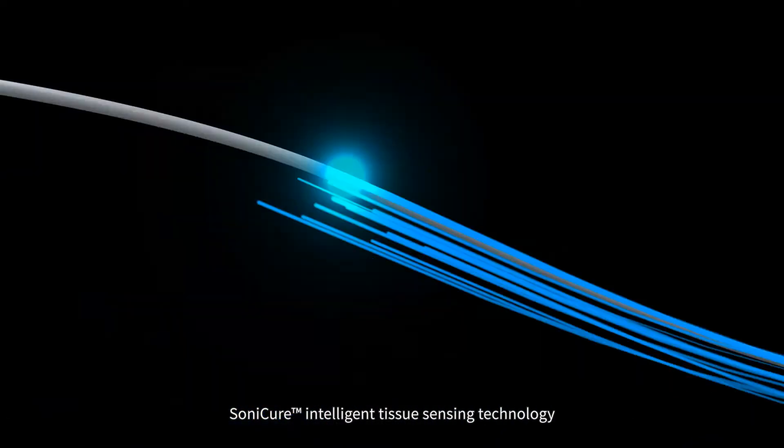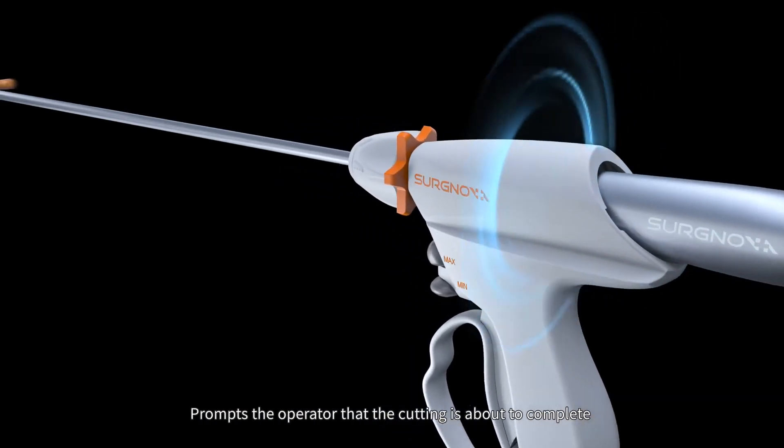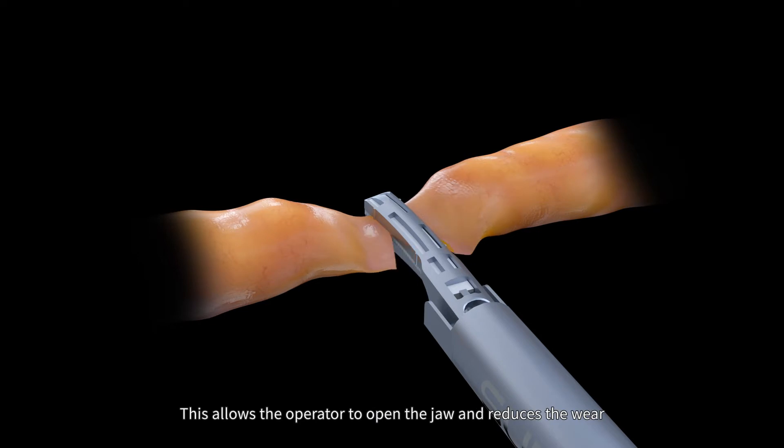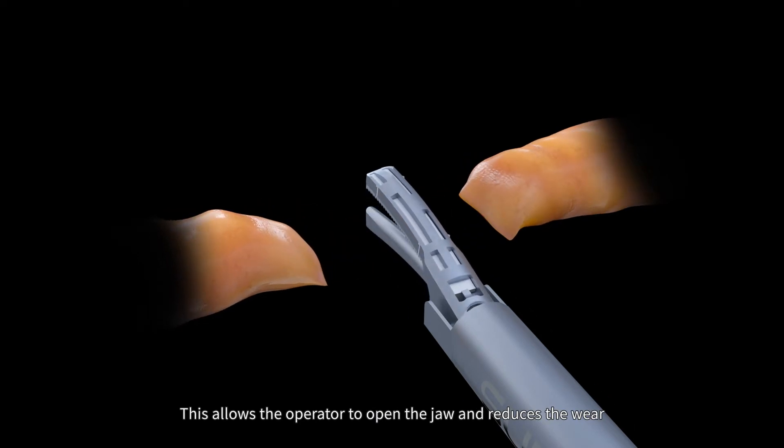SoniCure intelligent tissue sensing technology prompts the operator that cutting is about to complete by changing the tone frequency. This allows the operator to open the jaw and reduces wear.